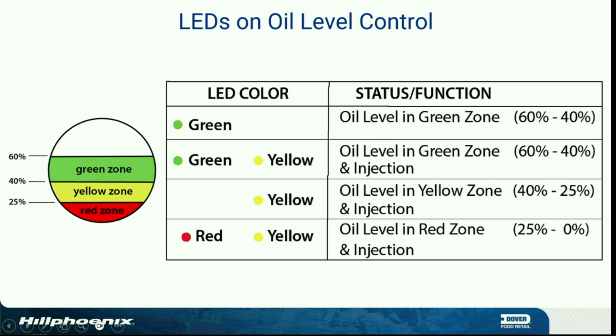All right, so going back, at 40%, yellow light comes on. At 60%, we shut off, okay? On the OMCs, don't go by the sight glass, and also on the Crewons. The Crewon is an optical switch. It's 130 bar rated. That switch, if you go at it, turns 90 degrees. There's a plate with 2 holes, and then the optics is behind it. So the oil representation in the sight glass is just telling you there's oil there. That's not the true level of your compressor. That's determined by the switch. And they're the exact same, 40 and 60%.